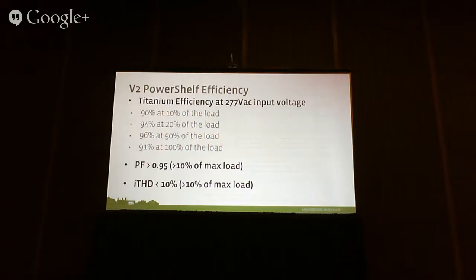The power supply efficiency meets the titanium standard, at 277 volts AC. At 10% loading we're 90% efficient, at 20% loading 94%, at 50% we're reaching 96% efficiency, and at 100% greater than 90%. Our power factor is greater than 0.95 when load is greater than 10%, and our THD is always less than 10% whenever we're greater than 10% loading.